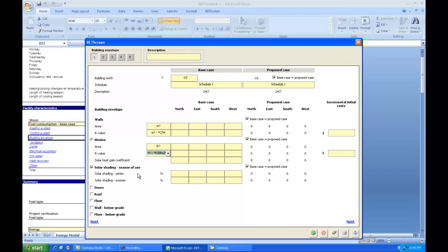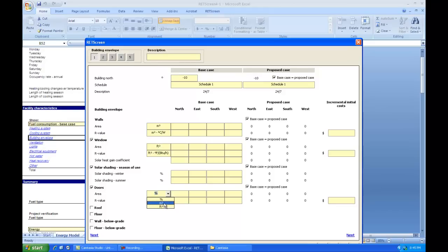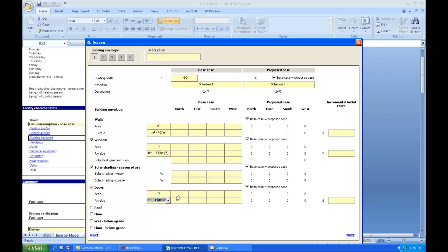Coming down here then we can model some doors. Click on that and open up the section for doors. And so doors again we'll do in either square meters or square feet. And we will select the imperial R value for the door. Now here we need to put in the total area of the door that faces in each of the directions. So we may have four or five doors, maybe two or three facing north. We need to add all those numbers together before we enter them in here.